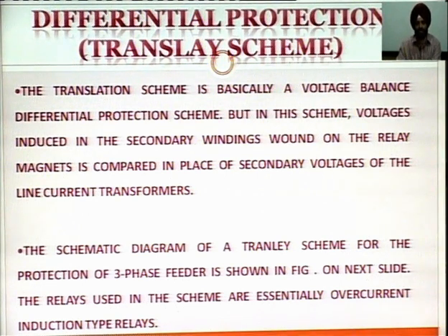The Translay scheme is basically a voltage balanced differential protection scheme, but in this scheme the voltage induced in the secondary winding wound on the relay magnet is compared in place of the secondary voltage of the line current transformer. The schematic diagram of the Translay scheme for the protection of a three-phase feeder is shown in the next slide.